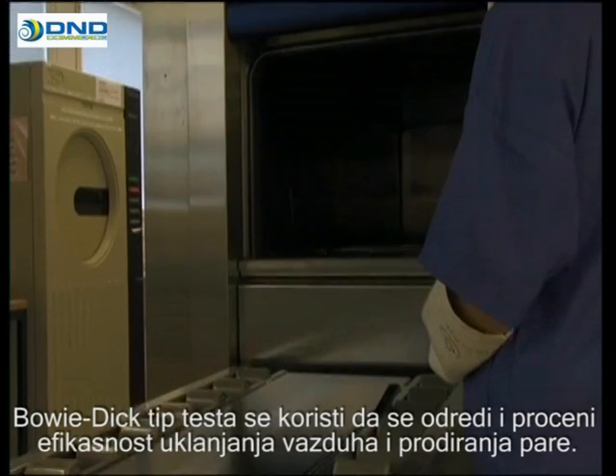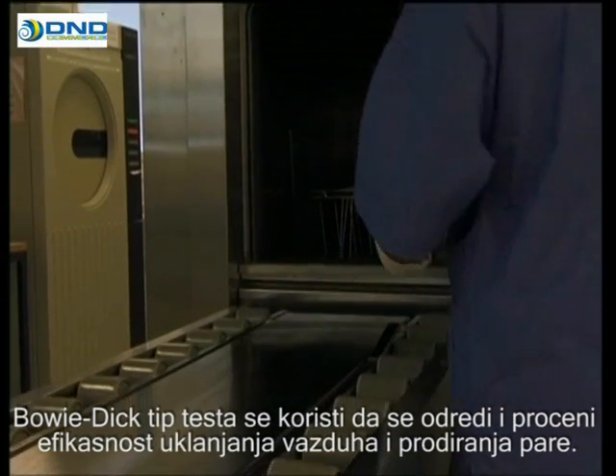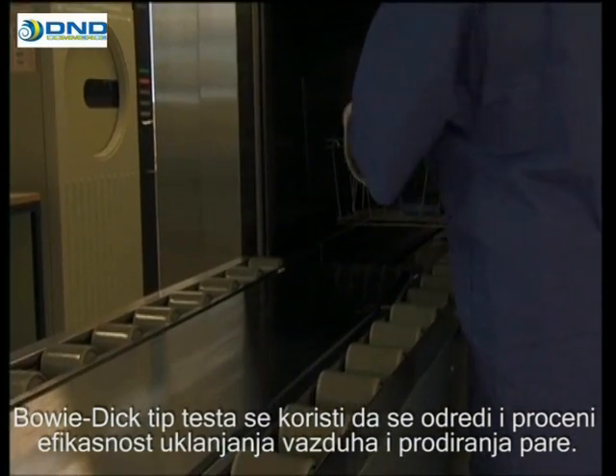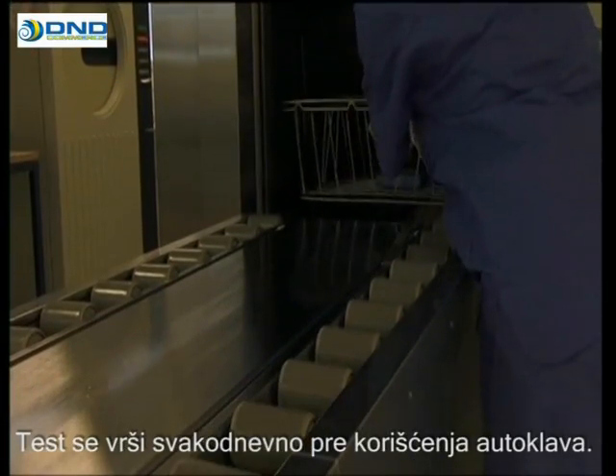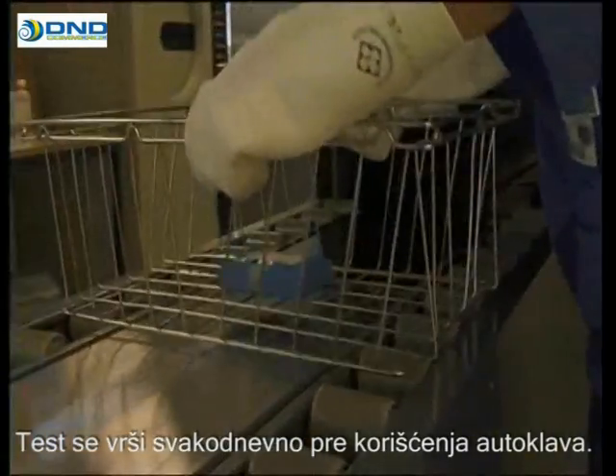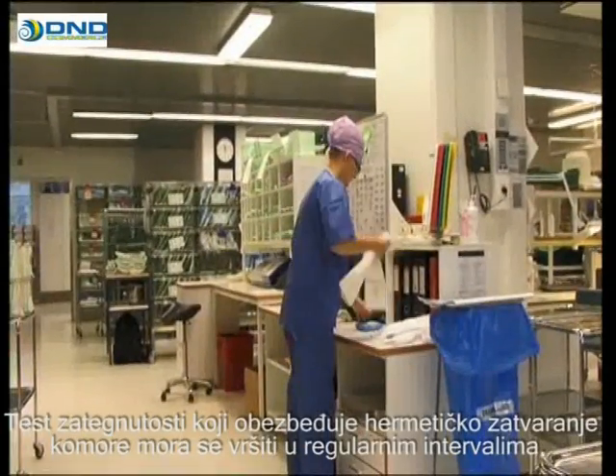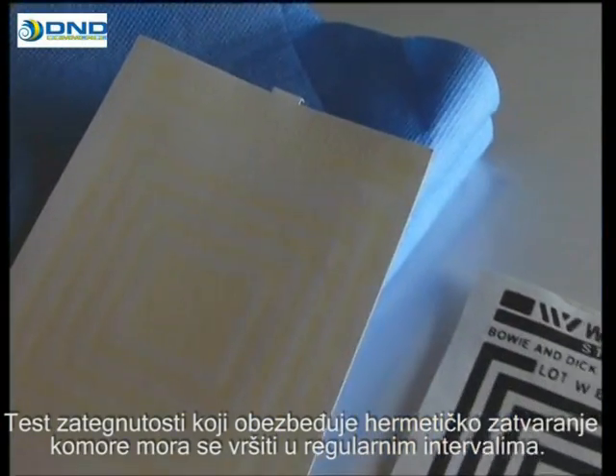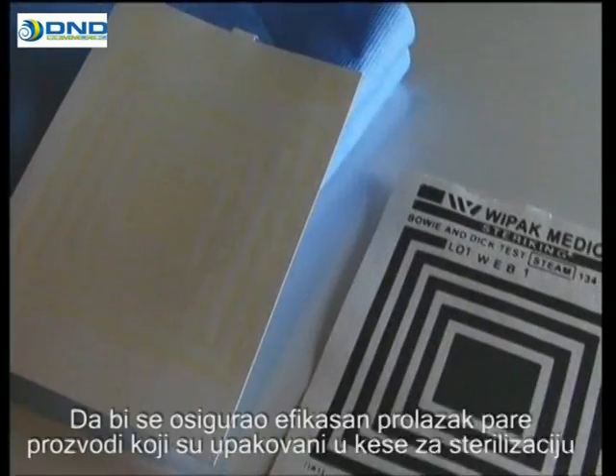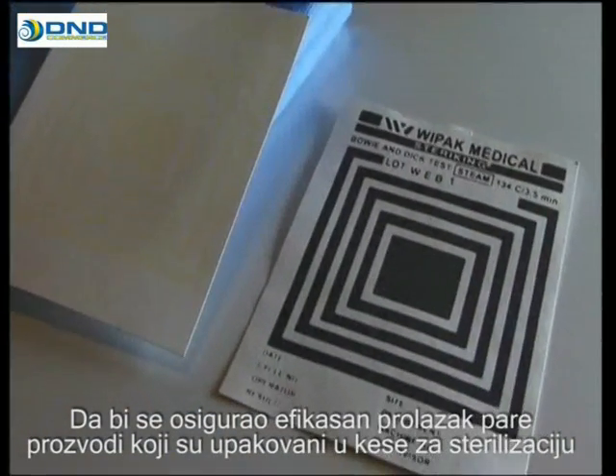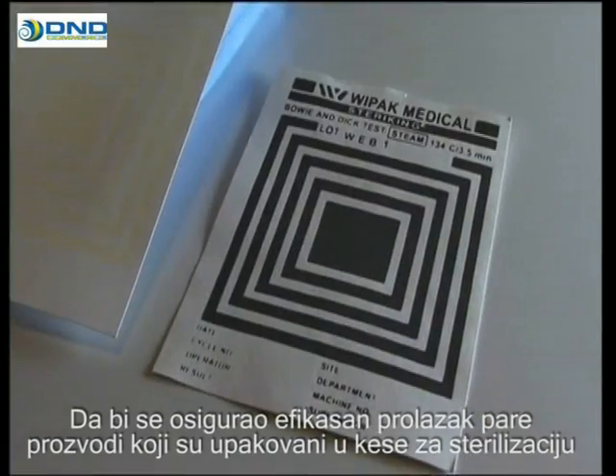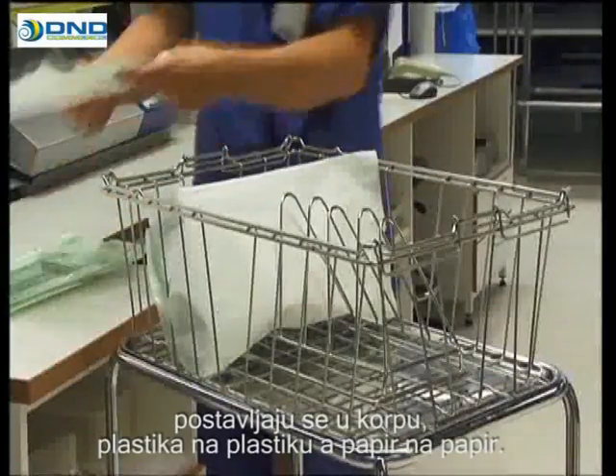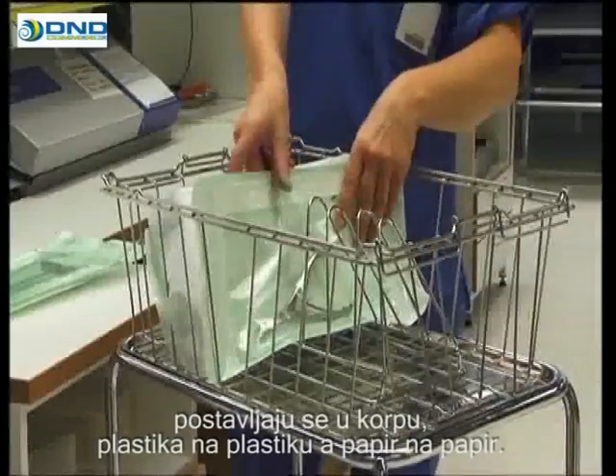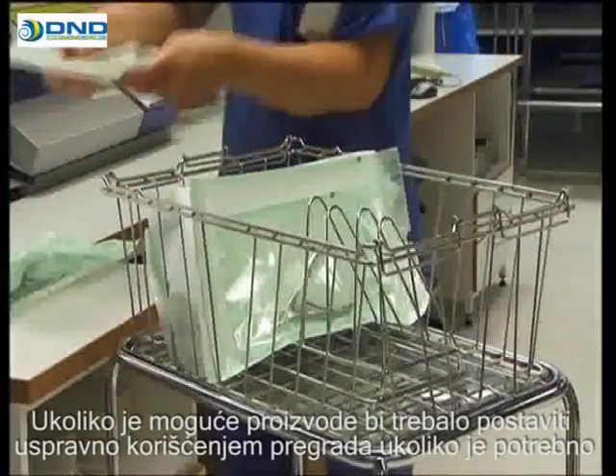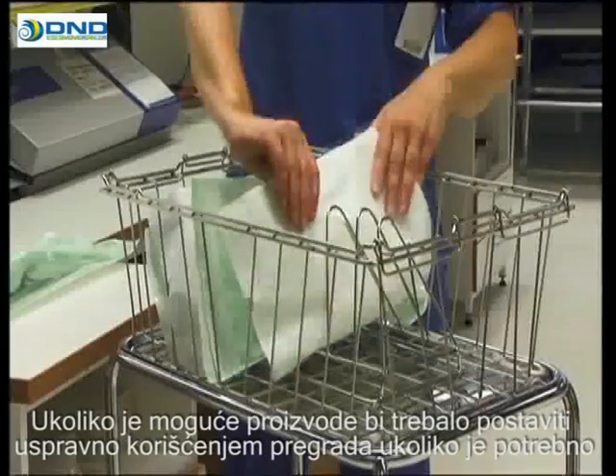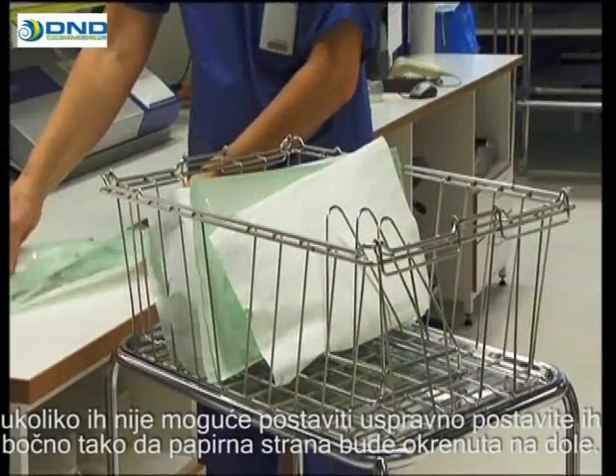The Bowie and Dick type test is used to check and assess the efficiency of air removal and steam penetration. The test must be performed every day before using the autoclave. The tightness test, to ensure the chamber is airtight, should be run at regular intervals. To ensure an effective passage of steam, the products packed in sterilization pouches are placed in the basket, laminate against laminate, and paper against paper. If possible, the packages should be placed upright, using partitions if necessary.